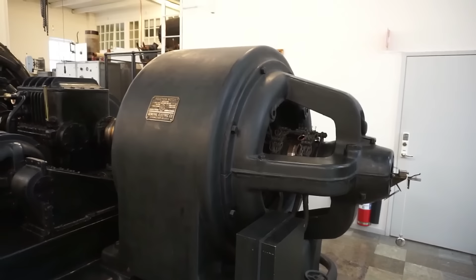We can control the speed of the motor in two ways. We can control the voltage to the stator winding by so-called transductors that are located in the transformer room, and they are connected in line with the power supply. The other way is that the windings in the rotor are connected to rheostats, and by that we can control the rotor resistance continuously, and by that adjust the rotor resistance and the torque of the motor. By that, we are going down to have a look at our auxiliary machines.